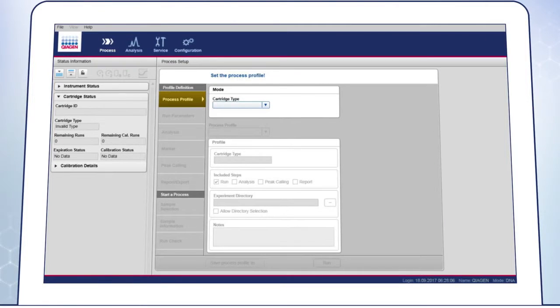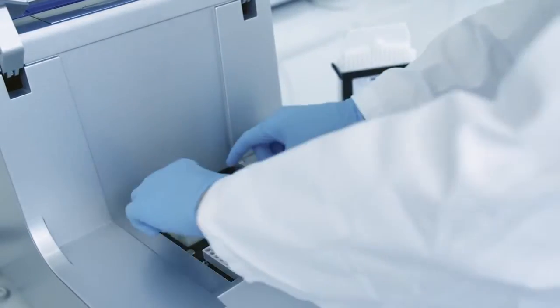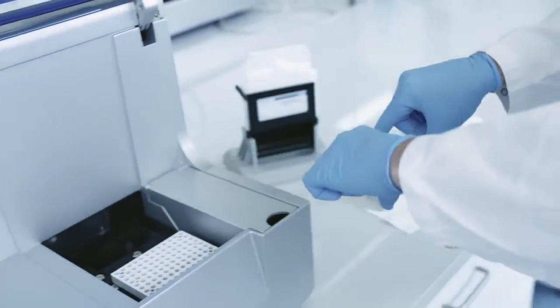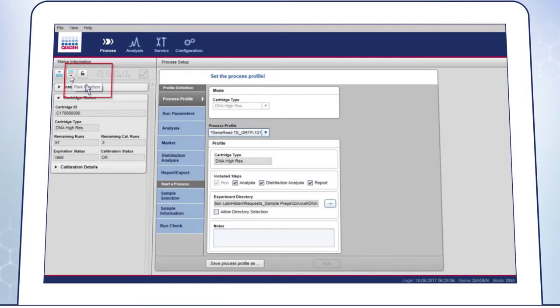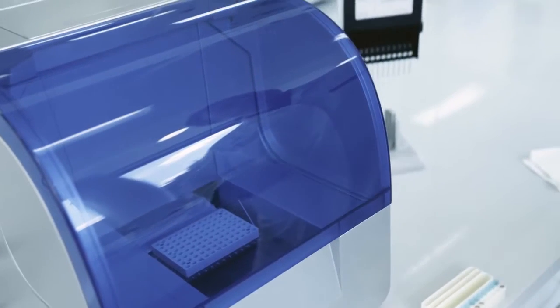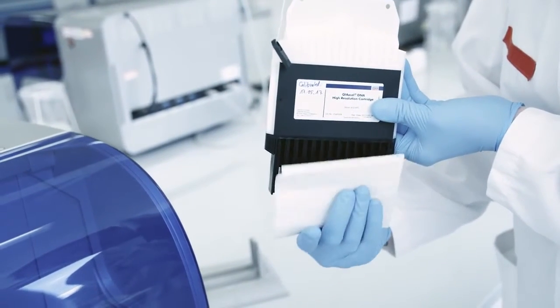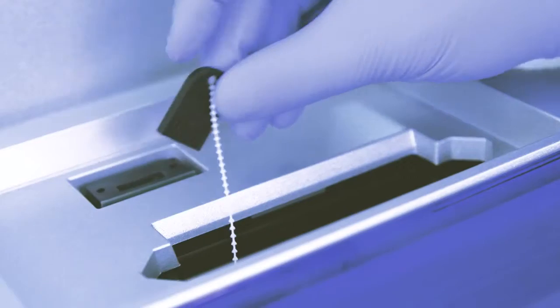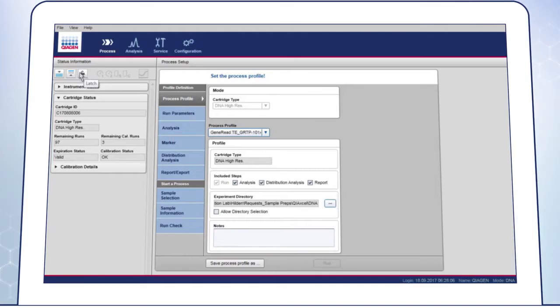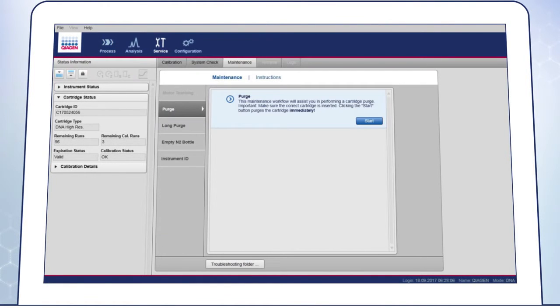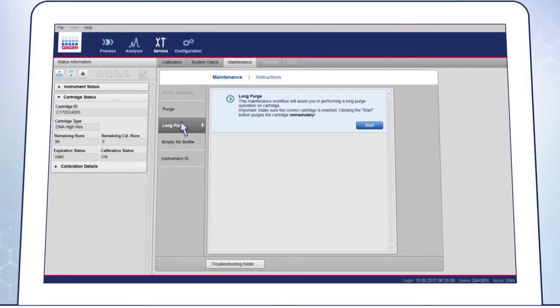Launch the QIAxcel Screen Gel software and click Load Position. Then remove the buffer tray from the buffer tray holder, place a soft tissue on the holder and click on Park Position. After the incubation, clean the capillaries and purge port before inserting the cartridge and Smart Key into the instrument. Click Latch if automatic latching is not active. Go to the service environment and open the Maintenance tab. Then click on Long Purge to start purging.